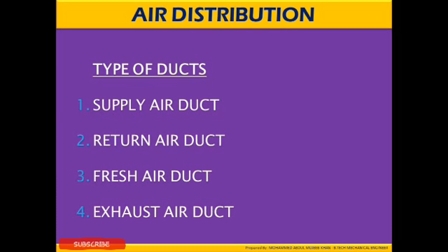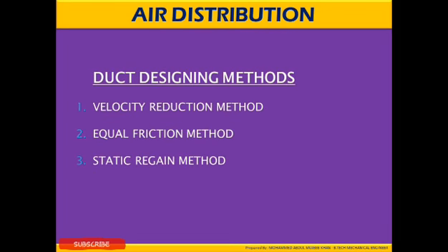Now let us see the different types of duct terminologies and their uses. The first is the supply air duct, return air duct, fresh air duct and exhaust air duct. Duct designing methods. Basically, the duct design sizing is done on three criteria: velocity reduction method, equal friction method, and static regain method. These are the three different methods through which duct design can be done.